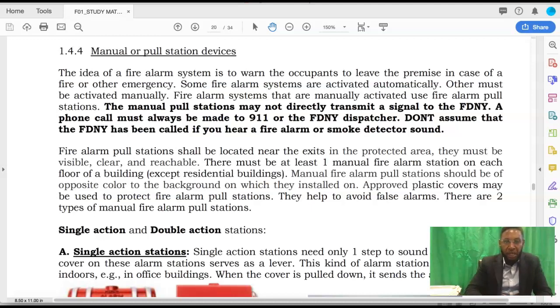The manual pull stations may not directly transmit a signal to the fire department. So like I said earlier, you need to shoot a phone call. A phone call must always be made to 911, or if you have a speed dial to the fire department dispatcher, great. But don't ever assume that a fire department may be called if they hear an alarm, or that a smoke detector automatically activated the fire department signal to know where the fire is coming from. You have to sound that alarm manually.